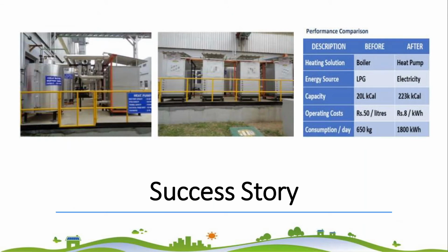Now I would like to narrate a success story of Aspiration Energy in a three-wheeler manufacturing plant. It is in a paint shop where they wanted 55 to 70 degrees Celsius maintained in the treatment tanks, and for that 85 degrees Celsius hot water had to be supplied. They were using LPG as the source for getting 85 degrees Celsius, about 650 kg per day of LPG.